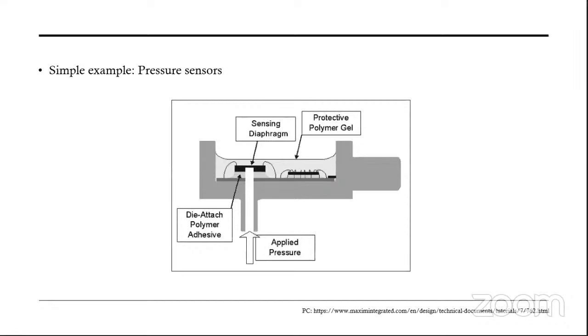You have several mechanisms for that. The first is a piezoresistive material, where according to the strain, its resistance changes. Imagine you make your diaphragm with a piezoresistive material, and the air pressure falls on it. When it deflects, its resistance changes, and if you give a supply across this diaphragm, as the resistance changes, you could easily sense the incoming pressure. That is the most simple way to implement a pressure sensor.